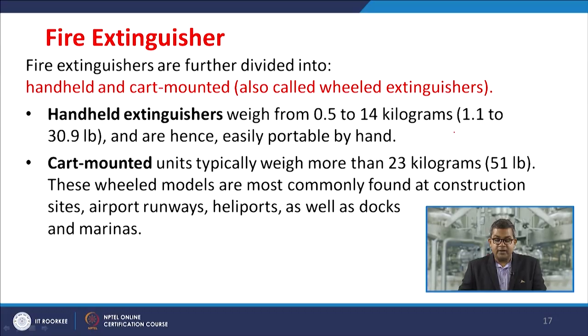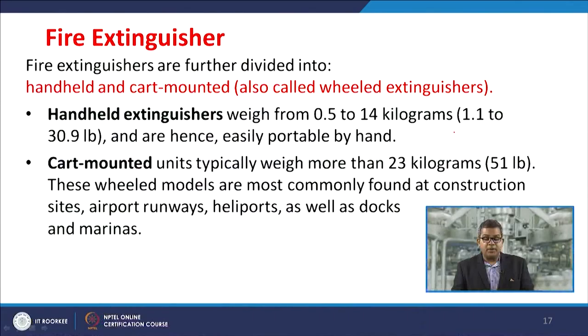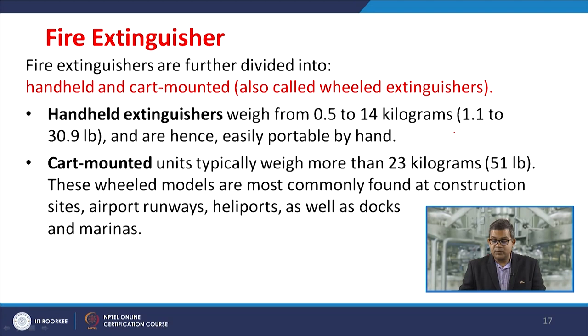Fire extinguishers are further divided into hand-held and cart-mounted (also called wheeled) extinguishers. Hand-held extinguishers weigh from 0.5 to 14 kilograms and are easily portable. Cart-mounted units typically weigh around 23 kilograms and are most commonly found at construction sites, airport runways, heliports, docks, and marinas — usually used for large fires in large establishments.